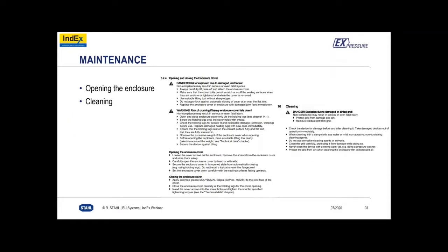So these important considerations are covered by R. Stahl. You do not clean the mesh. You do not wipe down the mesh. It is something that must not be touched. The covers, typical Ex d cover, take it off properly, bolt it up, torque it correctly. Do not damage the flame path. Do not damage the rupture plate, the mesh. Do not spray direct water jets at the rupture disc or at the mesh.